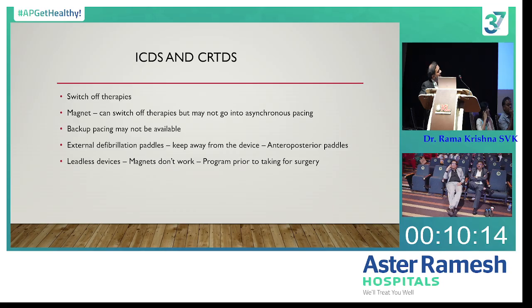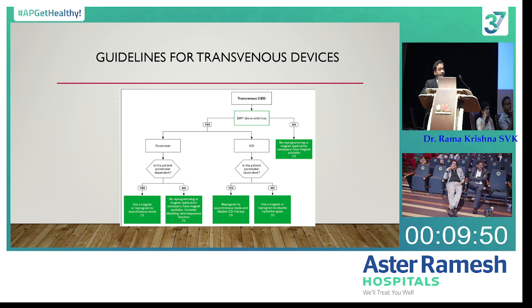When you use external defibrillation paddles, make sure that these paddles are far away from the device, at least around 7 to 8 centimeters away. Especially, anteroposterior paddles should be used in these patients. And leadless devices, we have quite a good number of patients with leadless pacemakers now. Remember, magnets don't work. You have to program the device prior to surgery. So these are the current guidelines that we follow. If we have a transvenous implantable device, if it is an ICD, you just have to reprogram. If the patient is dependent on a pacemaker, we reprogram to an asynchronous mode and disable the ICD therapy. If not, just use a magnet.